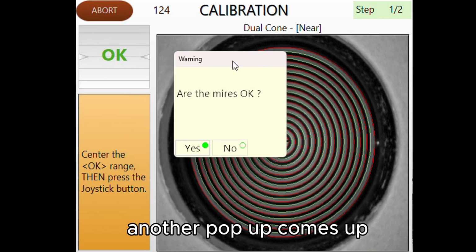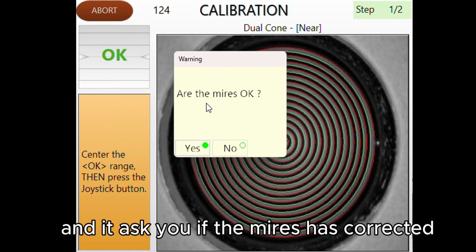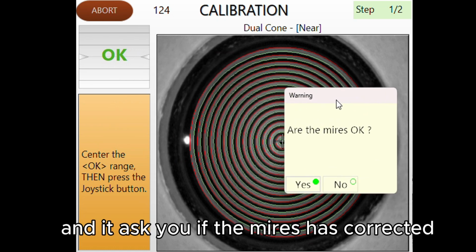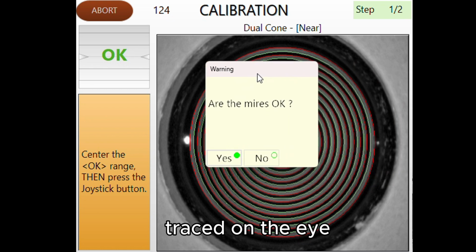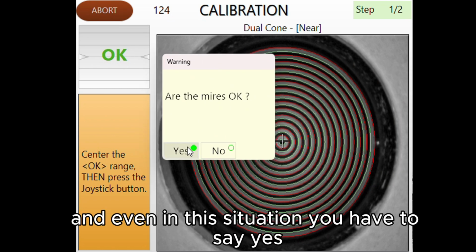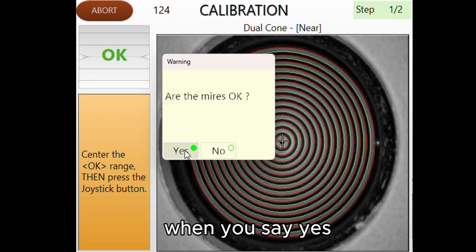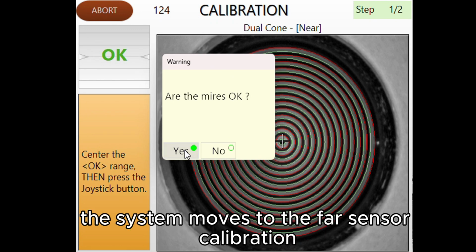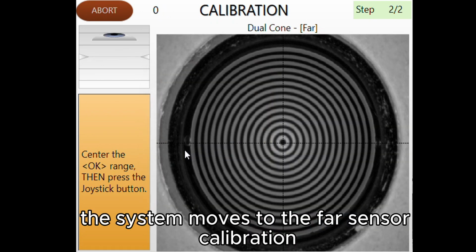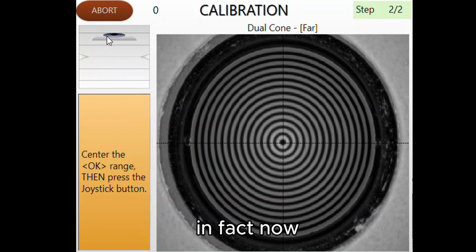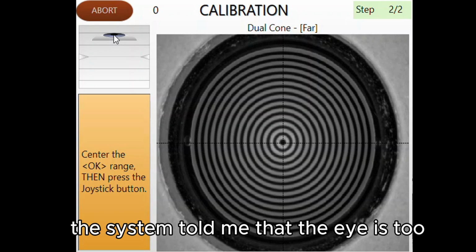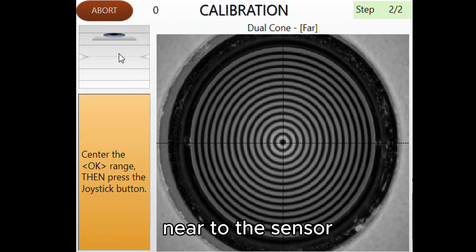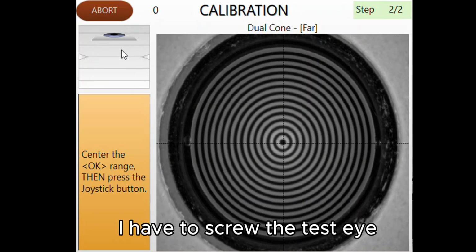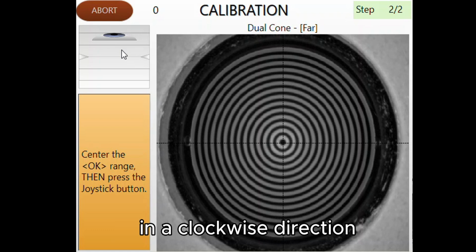Another pop-up comes up, and it asks you if the mire has been correctly traced on the eye. And even in this situation, you have to say yes. When you say yes, the system moves to the far sensor calibration. In fact, now the system told me that the eye is too near to the sensor. I have to screw the test eye in a clockwise direction.